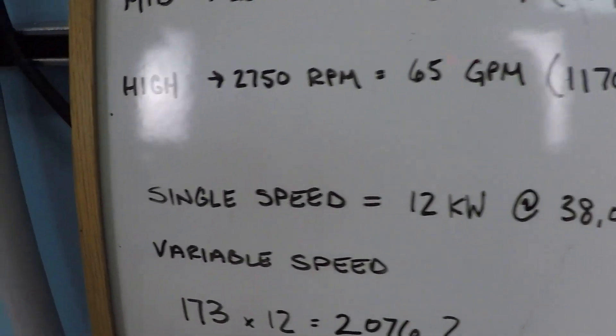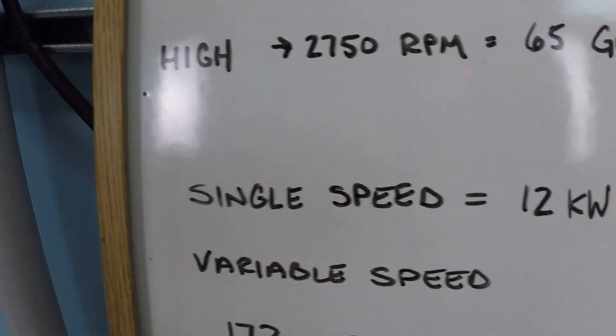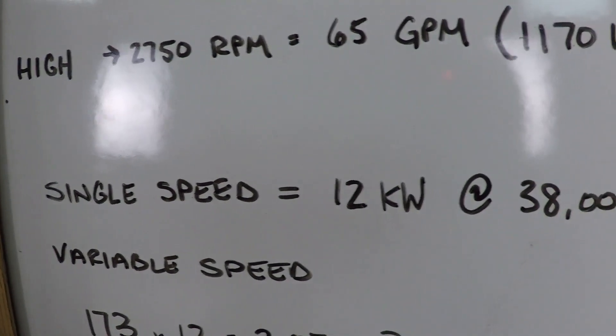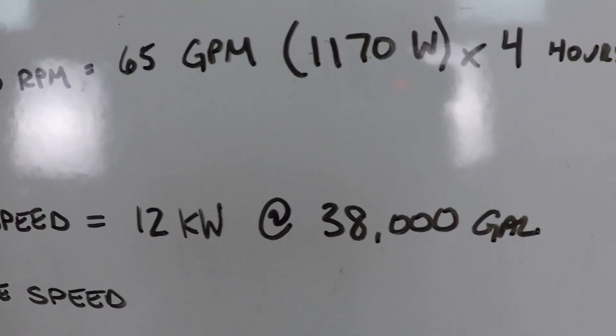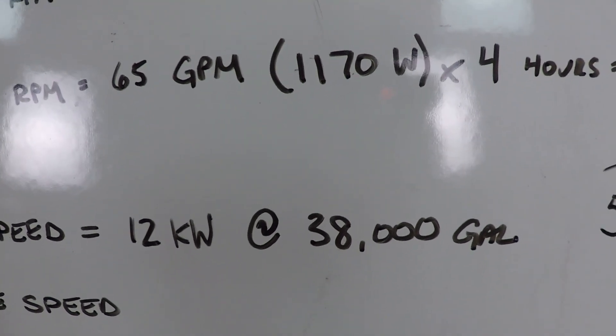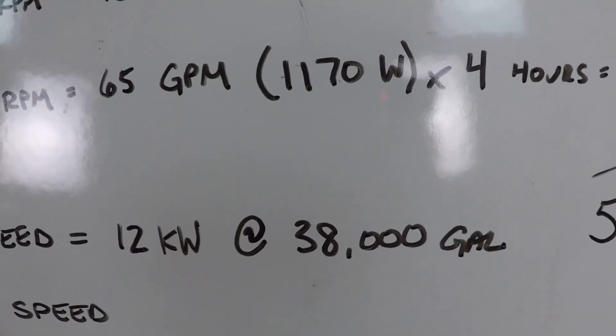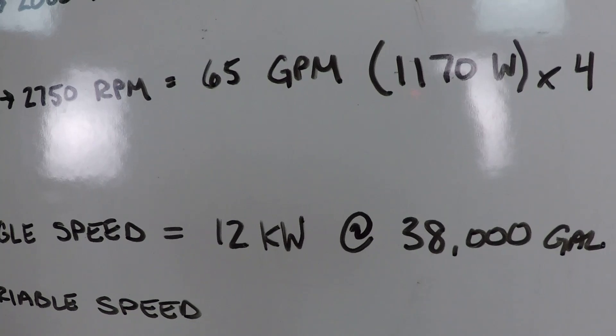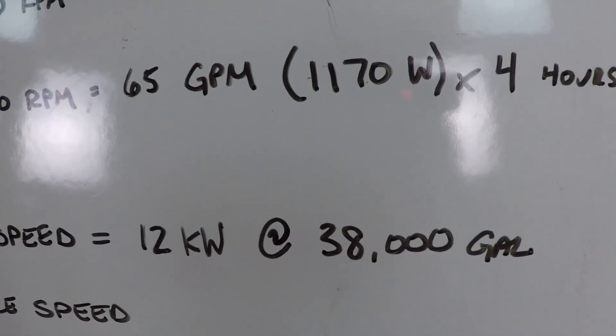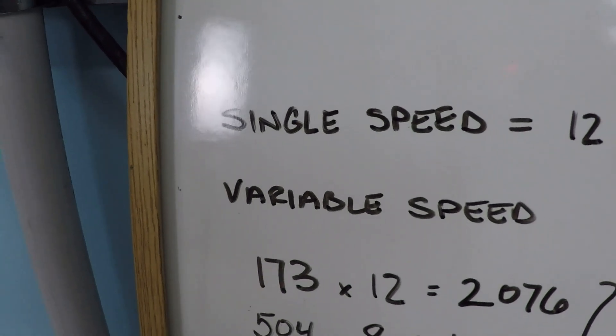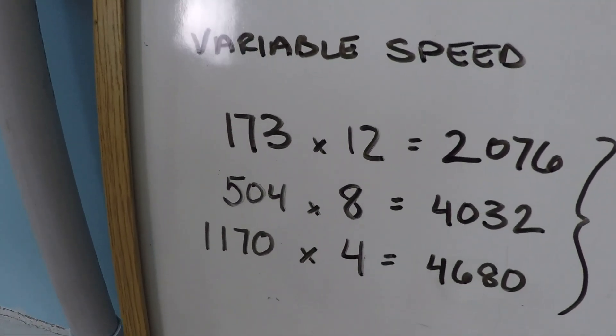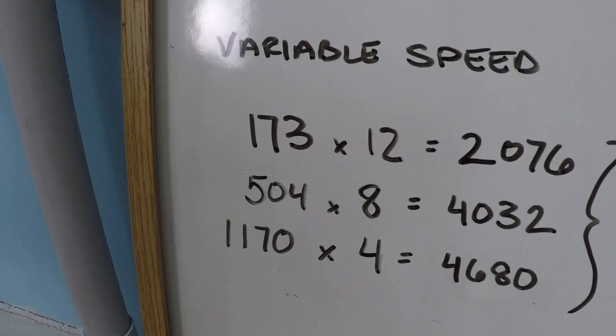Let's look at the power consumption for this. A single speed pump used 12 kilowatts of power to filter 38,000 gallons of water. That's the starting point here. That's I run my pump 8 hours a day, 12 kilowatts per day, and you get 38,000 gallons for it. With this optimized variable speed schedule, this is the power calculation.